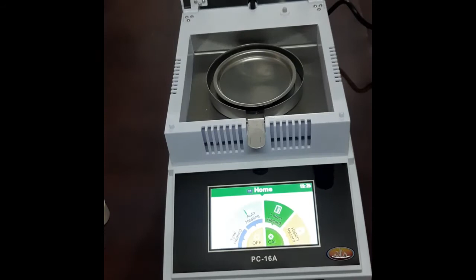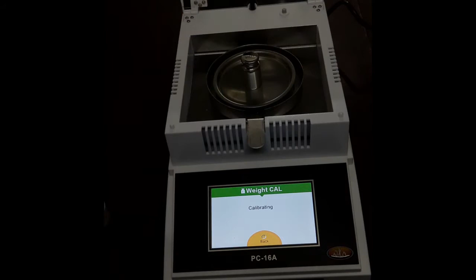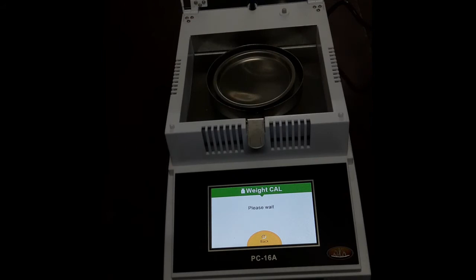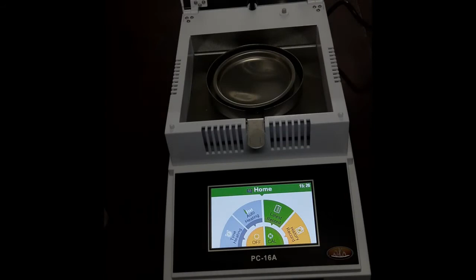In cal, if you want to do weigh calibration, press weight cal, and it will ask you to load the weight of 100 grams. The 100 grams weighing standard comes along with the instrument. Load the weight. It will go for the calibration. After calibration, it will ask you to remove the weight. After completion of calibration, the instrument will come directly into the main menu mode.